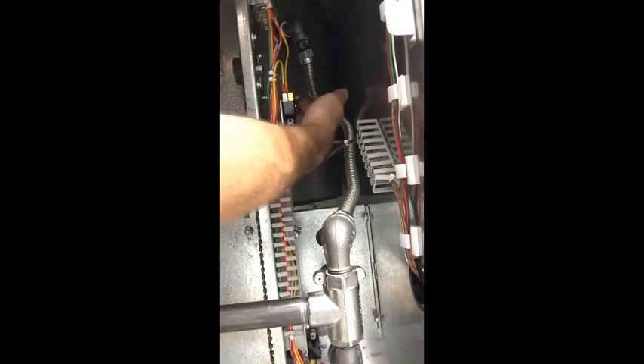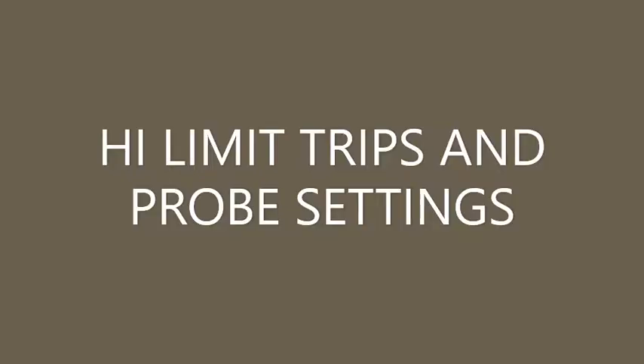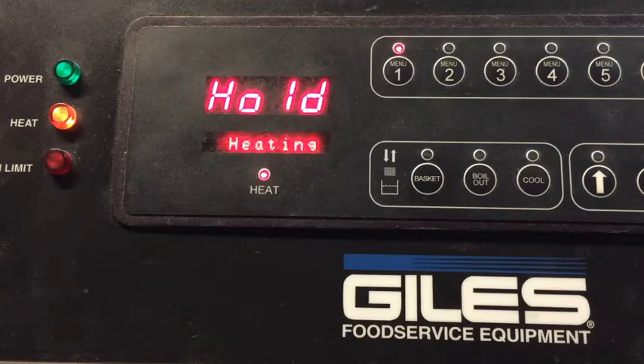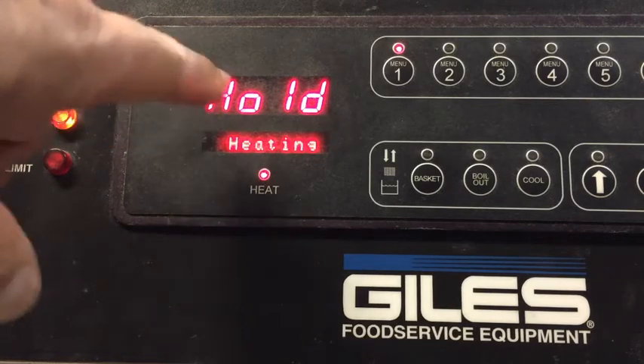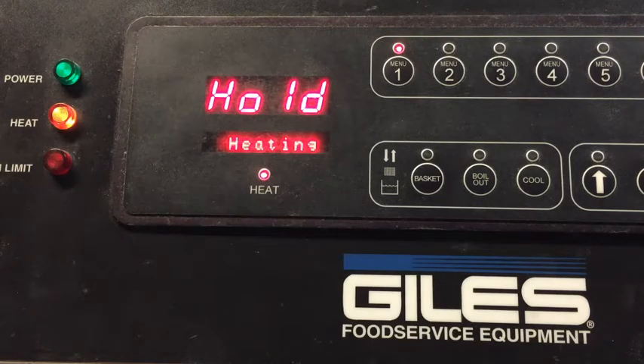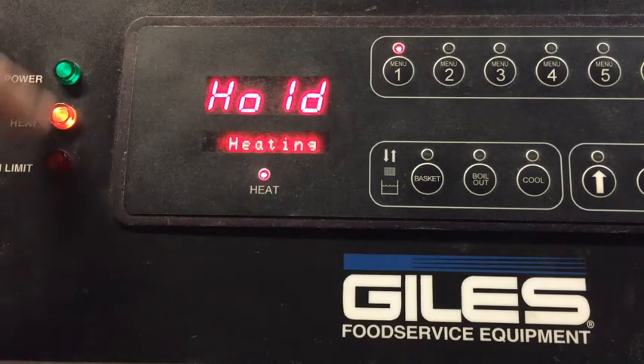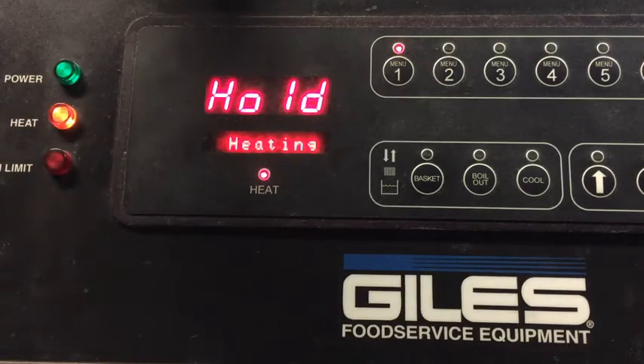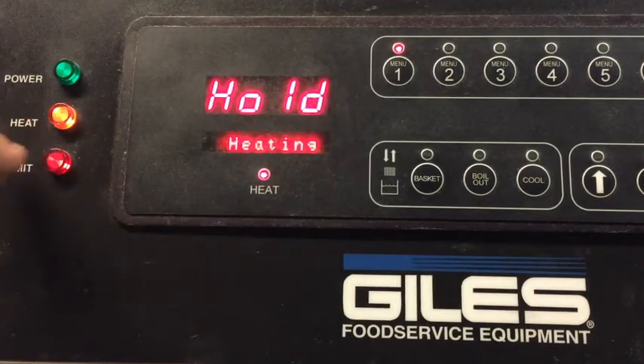Your element probe is tied in right, it goes in right here, insert in here, and then strap to the element. Now I just want you to know, regardless of which controller you have, the high limit function works the same. The high limit module, as mentioned before, is separate from the controller, so it will not send a message. You will not get a message here on your screen telling you that it's in high limit. Indeed, what will happen is you'll have the power, it's trying to heat, and then the high limit light will come on. When that comes on, you've dropped out the bottom contactor in the rear.